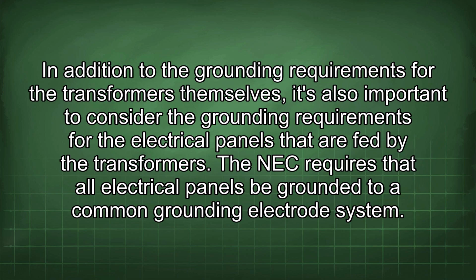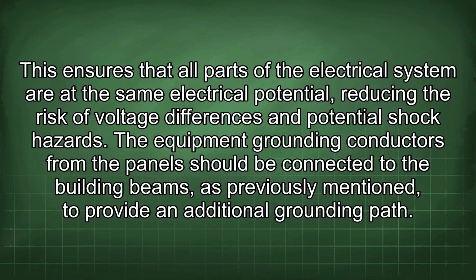In addition to the grounding requirements for the transformers themselves, it's also important to consider the grounding requirements for the electrical panels that are fed by the transformers. The NEC requires that all electrical panels be grounded to a common grounding electrode system. This ensures that all parts of the electrical system are at the same electrical potential, reducing the risk of voltage differences and potential shock hazards.